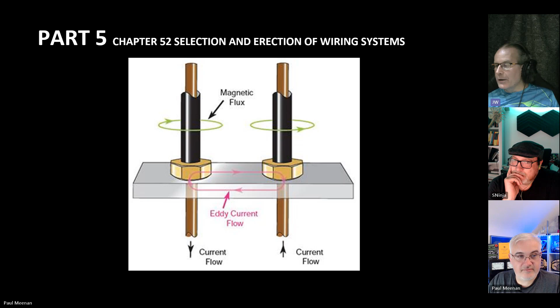The note is that for low voltage switchgear and controlgear assemblies to BS EN IEC 61439, conductors in AC circuits with a current rating not exceeding 200 amps can pass through separate holes, etc., in ferromagnetic enclosures. Currents above 200 amps, where they go through separate holes in a ferromagnetic material, need to have been verified by temperature rise test. So again, if it's under 200 amps, in theory, you can now shove them through separate holes.